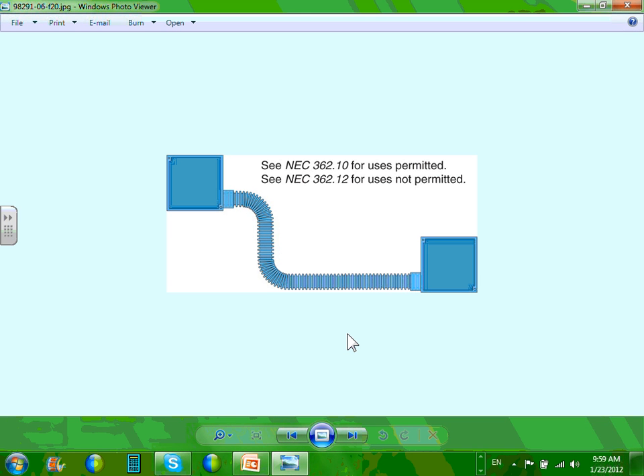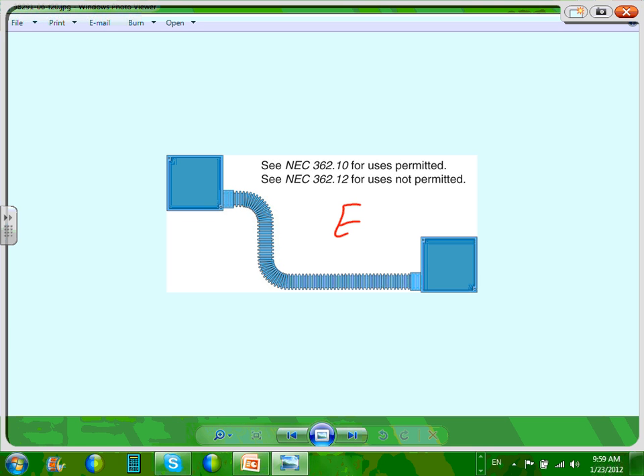The ENT, your ear, nose, and throat. ENT. We talked about this one, guys. Look at it. It looks like flex, except it's non-metallic. This is your ENT, electrical non-metallic tubing. It's a tubing. You pull your wires. This is non-metallic, so what do you need to pull with it? An equipment ground conductor.